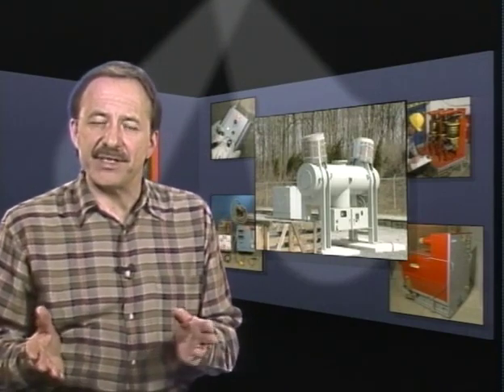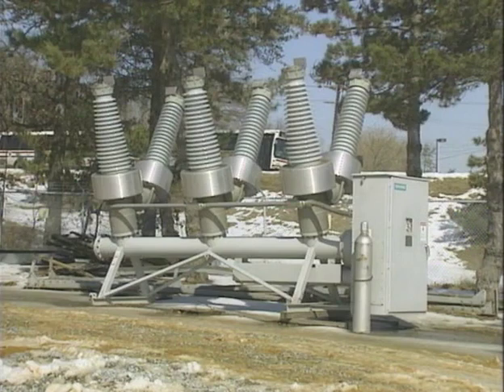Because of the obvious differences between types of circuit breakers and types of breaker operating mechanisms, some inspections and tests apply only to one type of breaker or breaker operating mechanism. But there are many tasks that are basically the same for all types of breakers and operating mechanisms. One of these is a circuit breaker acceptance inspection. A circuit breaker acceptance inspection is an inspection of the breaker that's performed when the breaker is received.